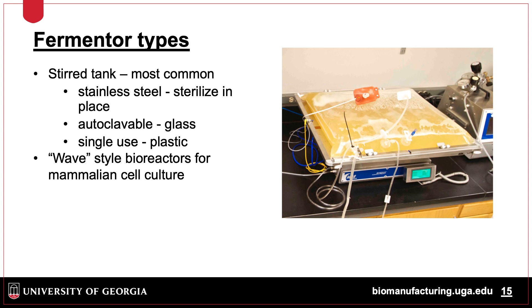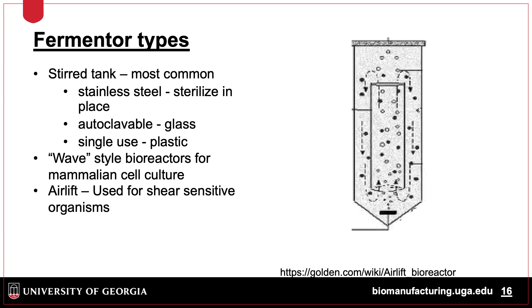Bioreactors are typically used for biopharmaceutical product production or as seed tanks for larger bioreactors. The airlift bioreactor uses gas bubbles to mix and oxygenate the media within the vessel, thereby resulting in less shear stress than fermenters. The bubbles typically originate from the bottom of the vessel and circulate inside to help with mixing and oxygenation. These bioreactors are used for growing shear-sensitive cells such as plant cells, since there are no impellers which cause shear stress.